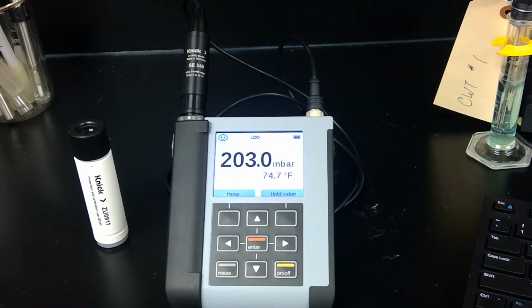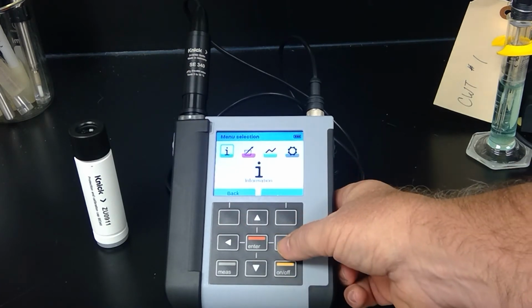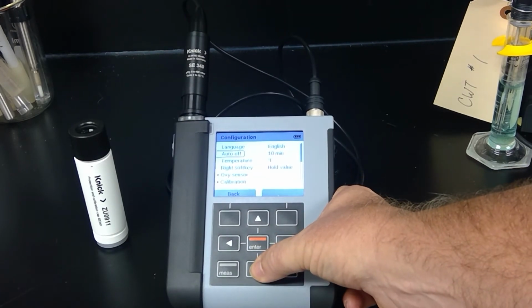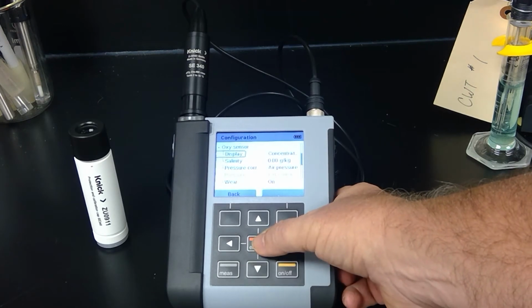Now, another advantage is that it does not have any electrolyte in the sensor. Being an optical driven DO sensor with no electrolyte, you do not have to worry about PMs in the sense that you have to remove the cap, replace electrolyte, replace the membrane. So it makes it a very, very low maintenance device. And of course, being portable, you're able to take it into the field and use it for grab samples.